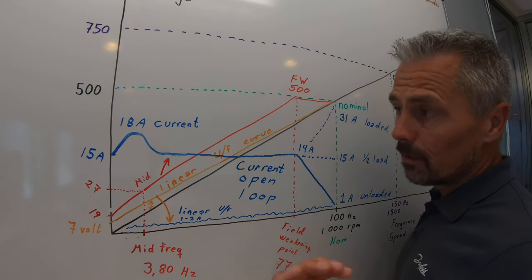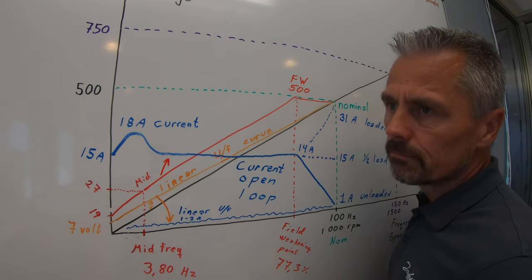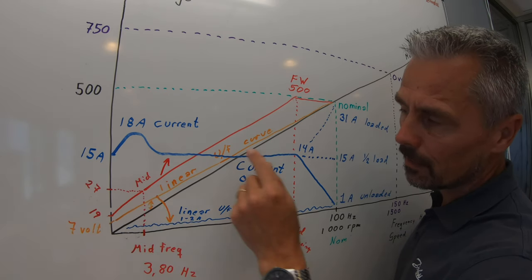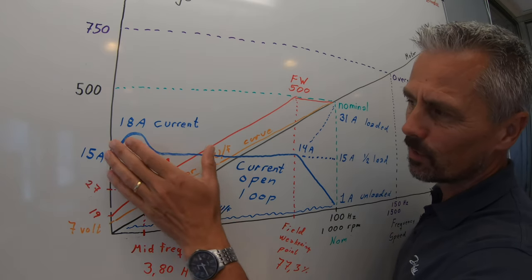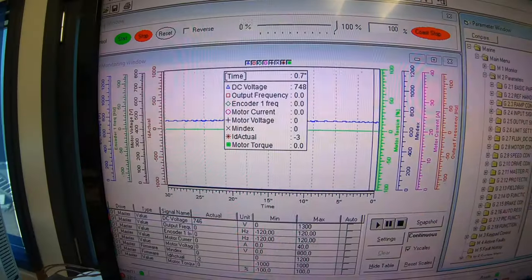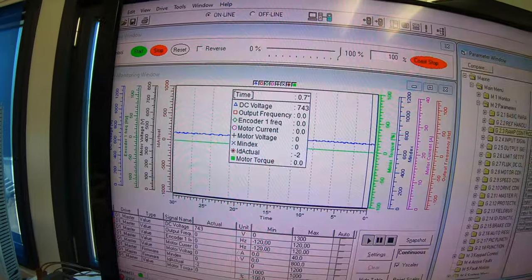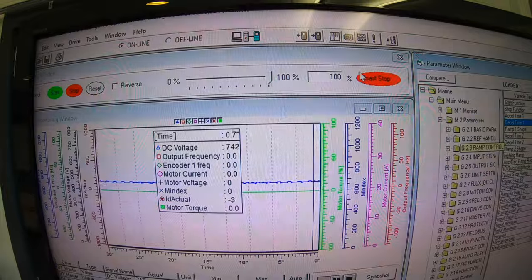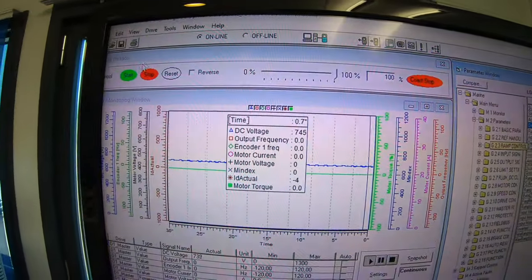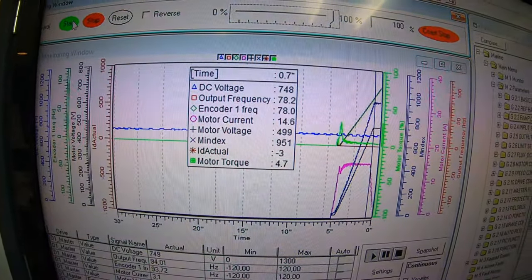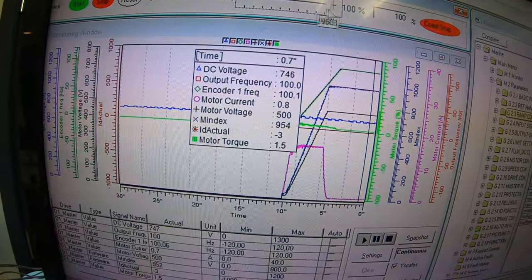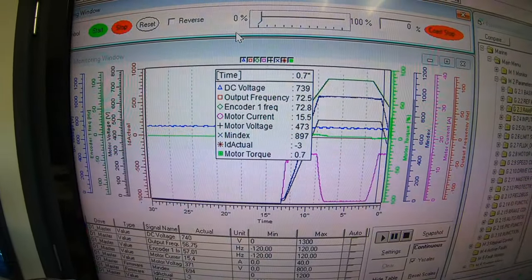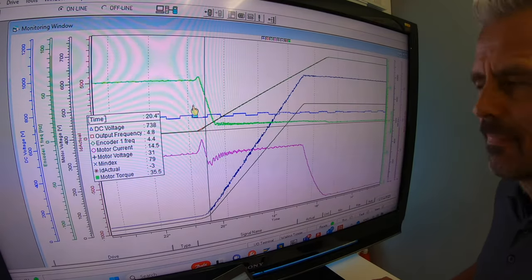We are now running without a resolver. The advantage is less complexity. The disadvantage is that we have a high reactive current even at low speed references. So the efficiency on the motor is not the best on the lower power or torques. To be able to see the UF curve more in clarity, easier to compare to the whiteboard, I will now start the motor going a ramp for 5 seconds up to 100 speed. And we go straight down again, just to see how our UF curve looks like.